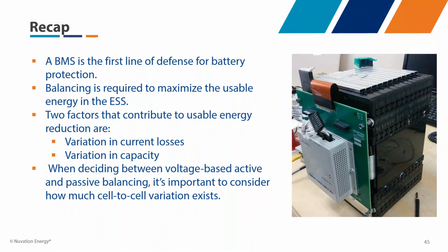We've had systems in the field where you see slight differences in cell voltages, and from that you can calculate differences in usable capacity per cell, which can feed into algorithms such as remaining useful life of a system. This can be highly useful for financial analysis and economic predictions of the system.